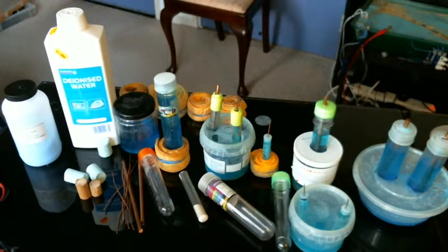The electrical potential of copper in a saturated solution of copper sulphate has a value that can be compared to other metals in their own salts, and these provide a list that can be used internationally. Steel has a corrosion potential that depends on the acidity of the electrolyte and will not corrode if electrical charges cannot leave the steel. The cathodic protection industry uses copper in a saturated solution of copper sulphate as a known reaction to compare with steel in an electrolyte when measuring a voltage.